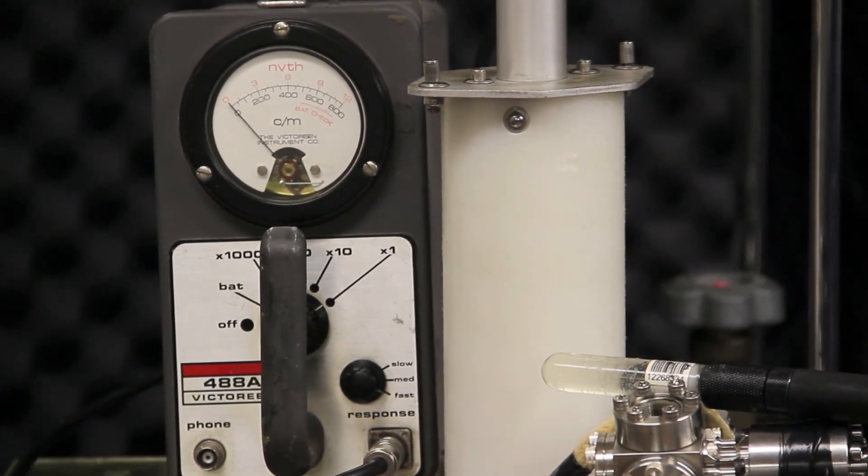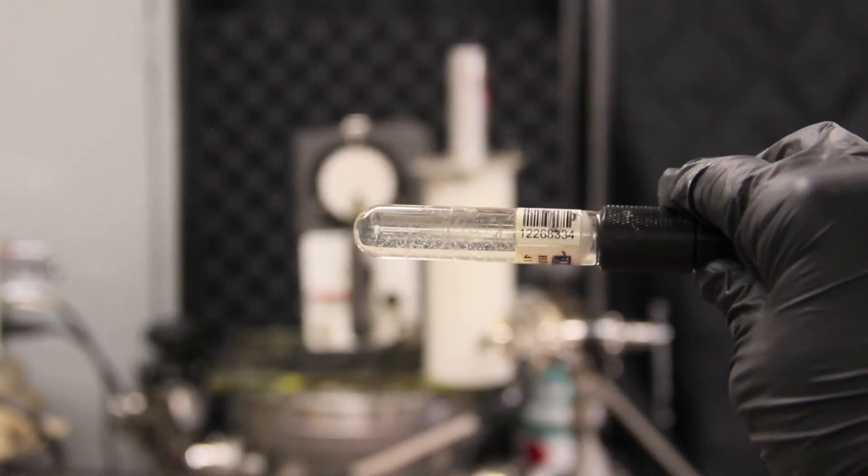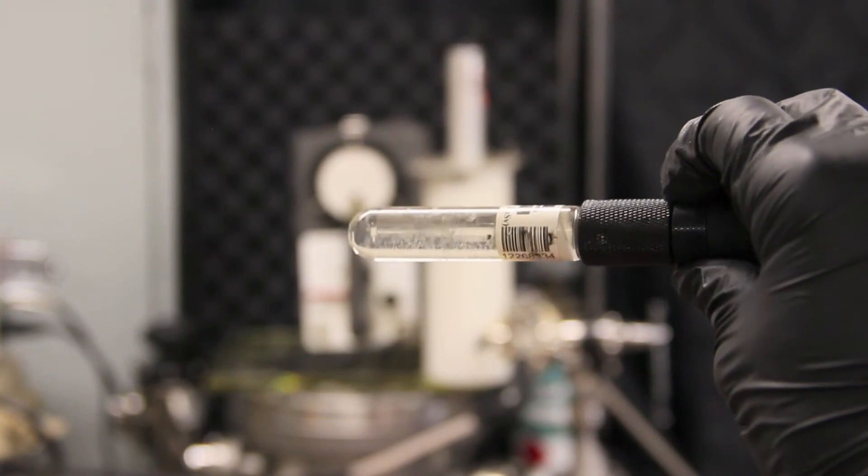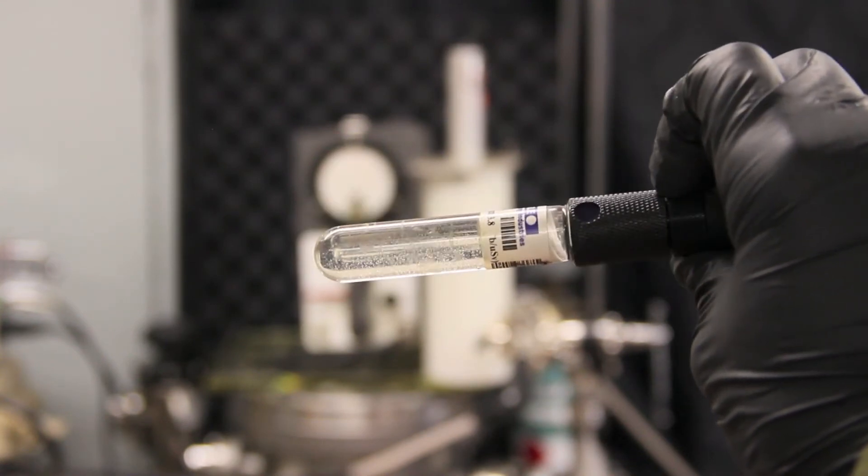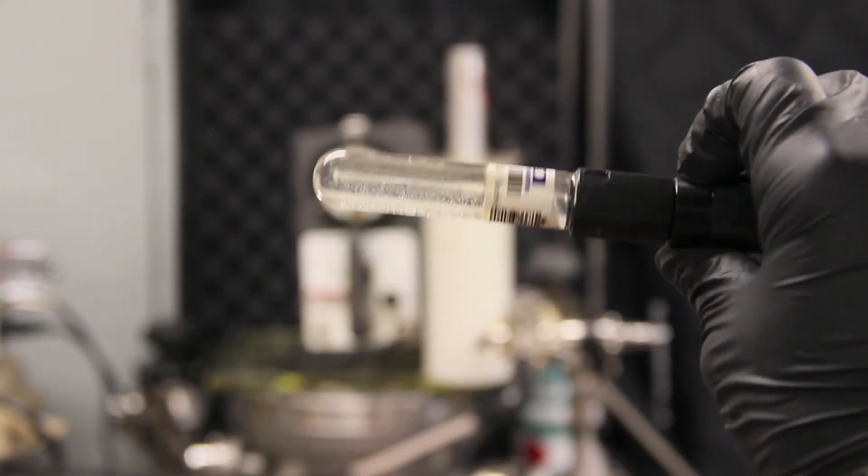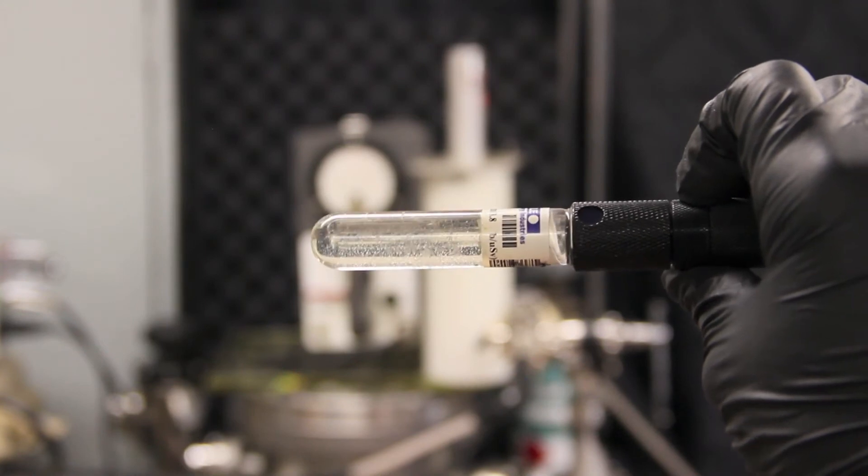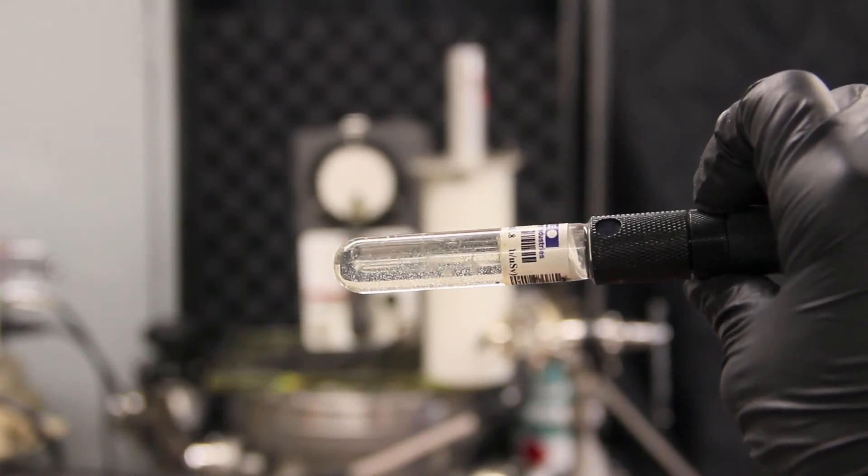On the bubble detector, what may look like bubbles right now, I will bring it a little bit closer just to show, but there are actually burns from previous runs, how warm it got. So as you can see there are no bubbles, just a few superficial burn marks on there. And it still detects just fine. Got a reading on it a couple minutes ago, so here we go.